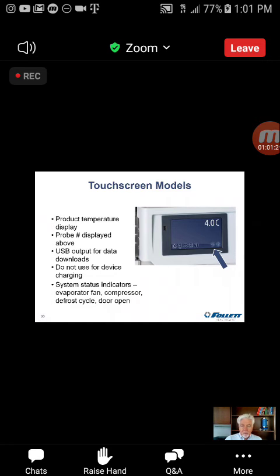System status indicators, I mentioned this on the basic control system here. We're doing the same thing, but we're doing it graphically. The fan blade means the evaporator fan motor should be running. A snowflake means that the refrigeration system should be running. And a melting snowflake means that the unit is in its defrost cycle.